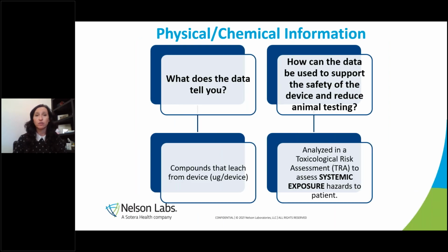So what does the data tell you? If you get a chemistry report, it's a list of compounds that were identified and how much came off the device. Then from there, you do have to step into a toxicological risk assessment. So chemical characterization testing is a twofold process. You do the extractables and leachables, or E&L, testing, and then you have the data evaluated by a toxicologist. The toxicologist can assess the data to understand the systemic exposure to the patient.